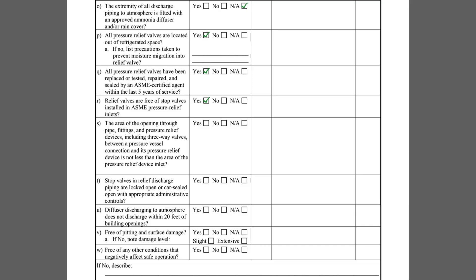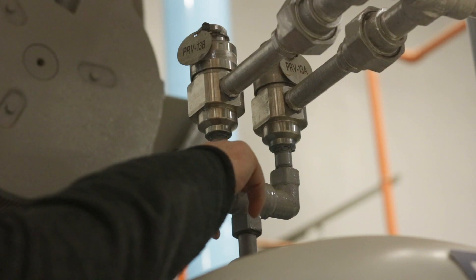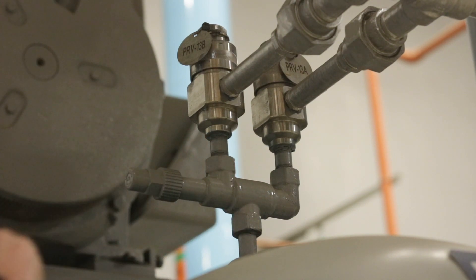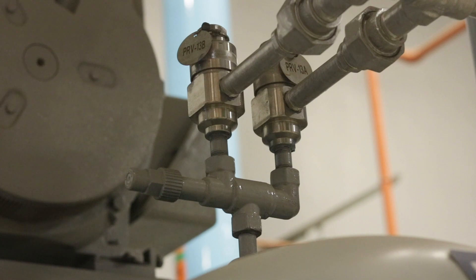Item R inquires if the inlet to each relief valve is free of stop valves which, if closed, would render the valve ineffective. Three-way relief isolation valves are acceptable since they do not allow both relief valves to be simultaneously isolated.